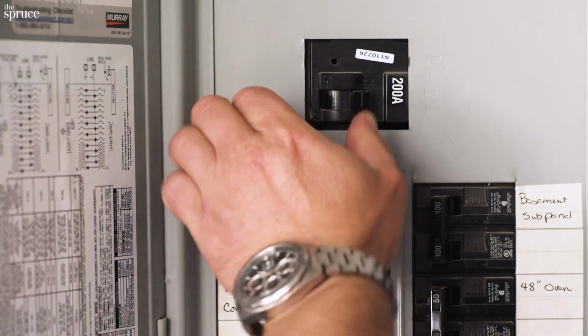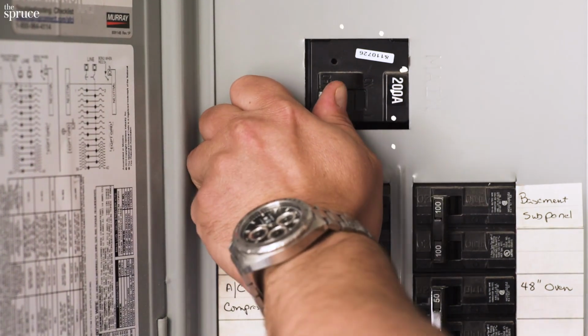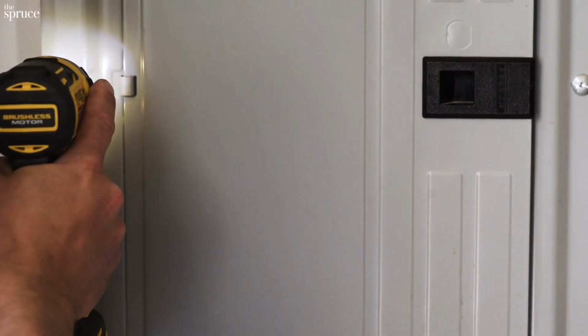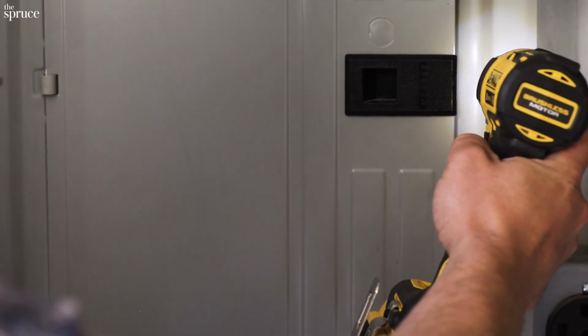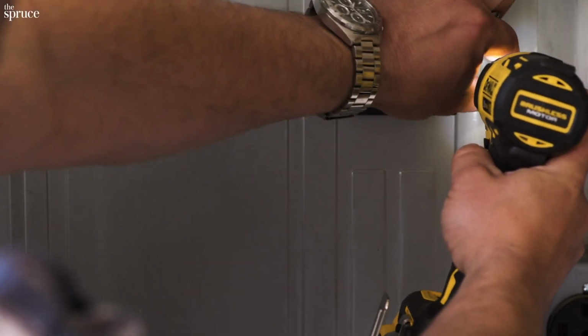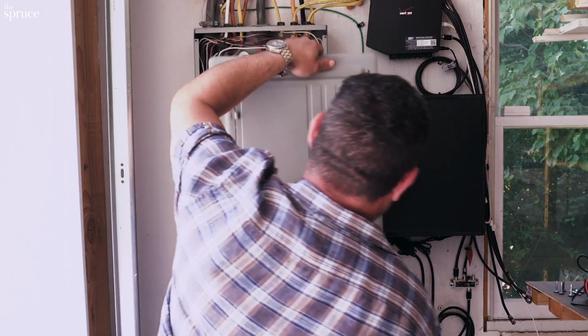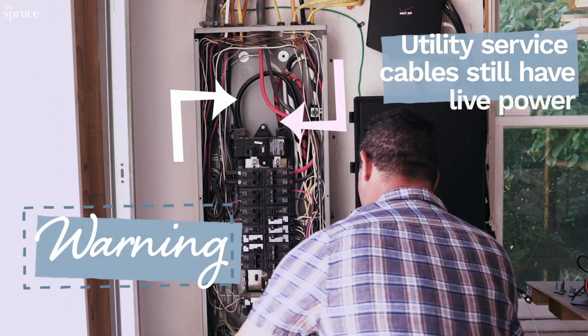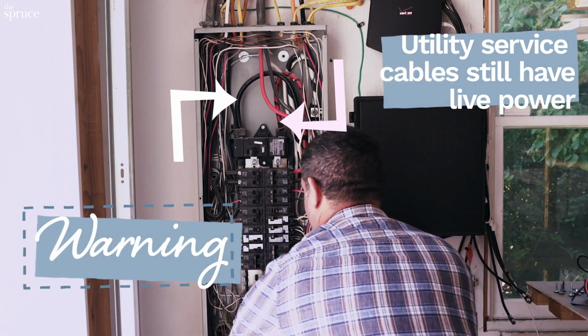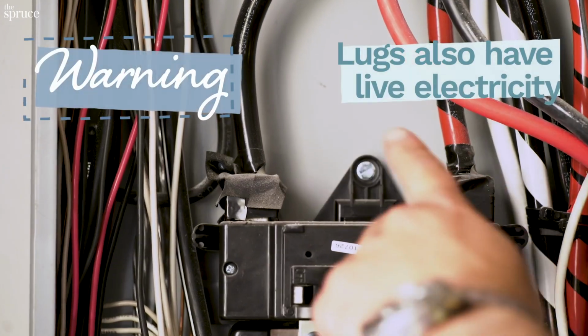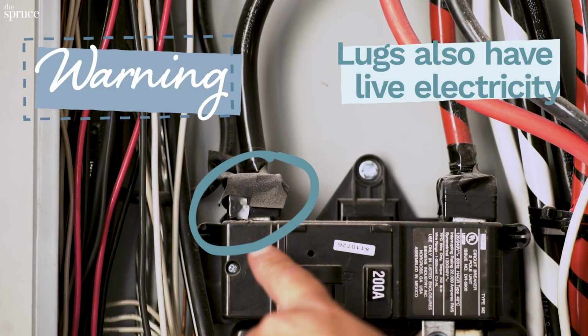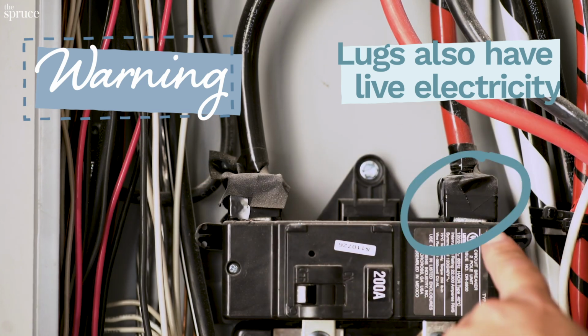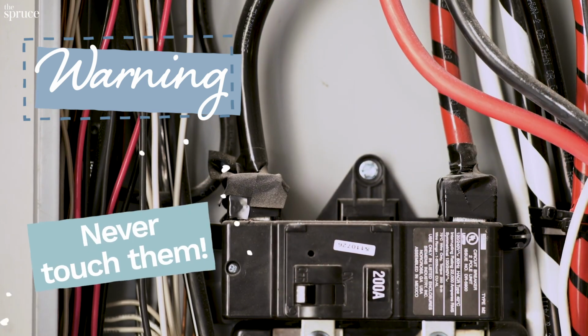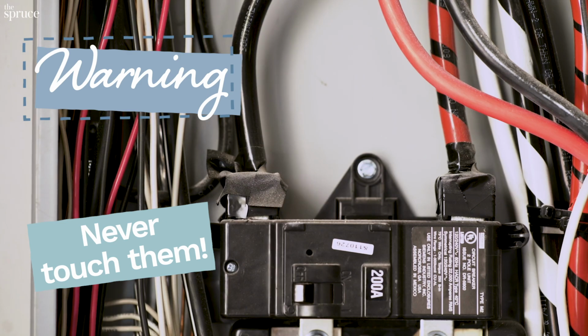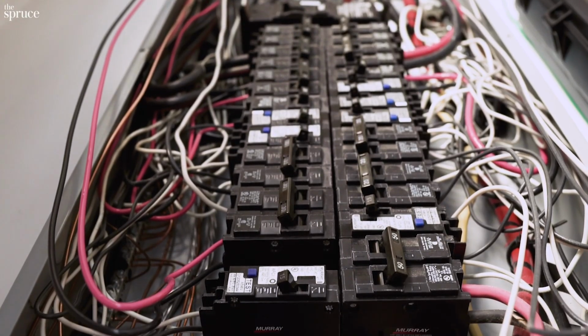The first thing to do is to turn off the main circuit breaker inside the panel and unscrew your panel cover. The main breaker shuts off power to all the branch circuits in your panel. But power is still running in the utility service cables, and power is also running where they connect to the main breaker in the service lugs. Our lugs are covered with electrical tape so you can't see them, but they're hot. Never ever touch the service cables or the lugs when you're working inside your panel.